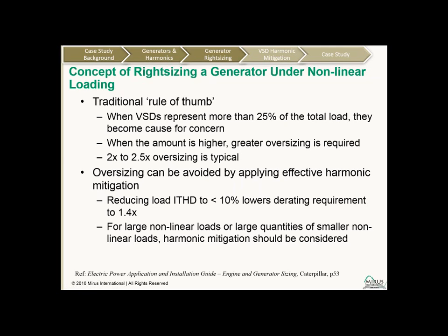So this is the traditional rule of thumb in a right-sizing approach for generators. When a VSD represents more than 25% of the total load, they become cause for concern. This is wording that came straight out of a generator manufacturer's application and installation guide. When the amount is higher, then greater oversizing is required, and 2 to 2.5 times oversizing is typical. They also mention that oversizing can be avoided by applying effective harmonic mitigation.